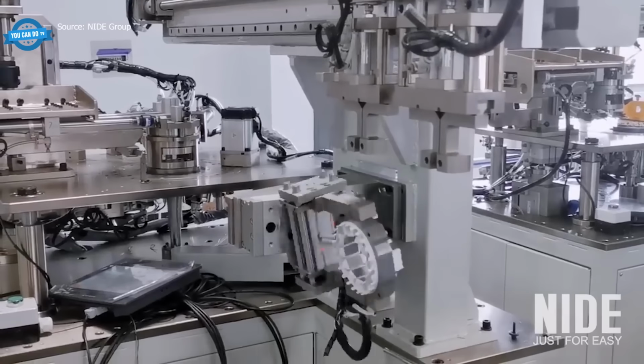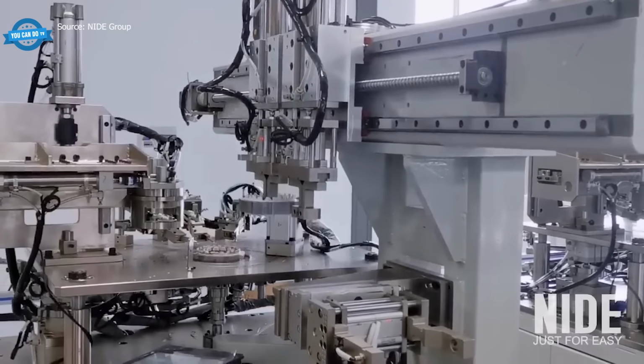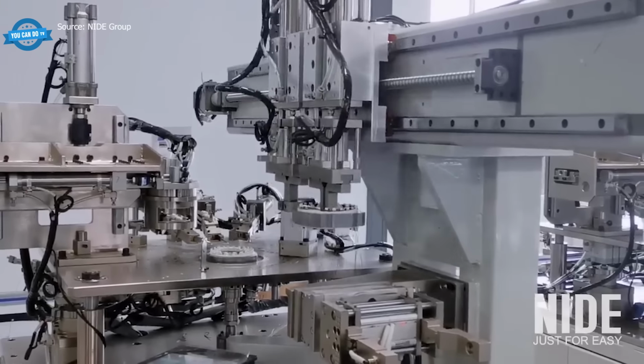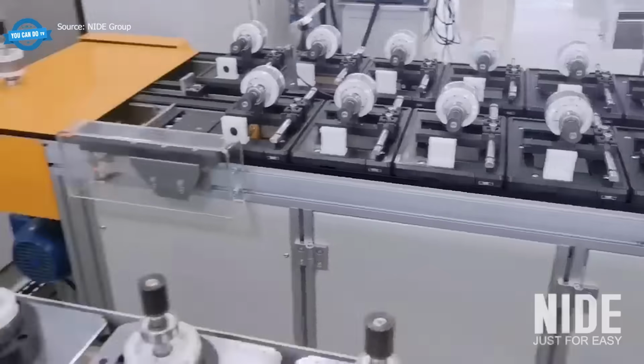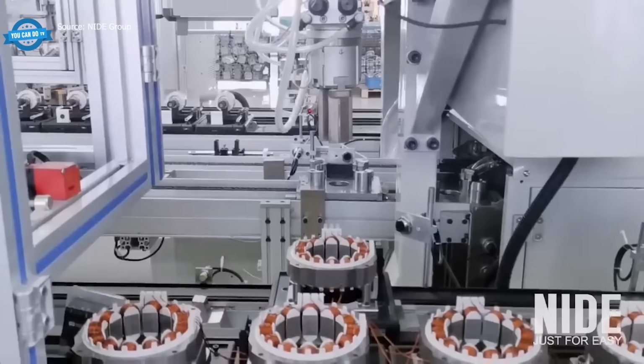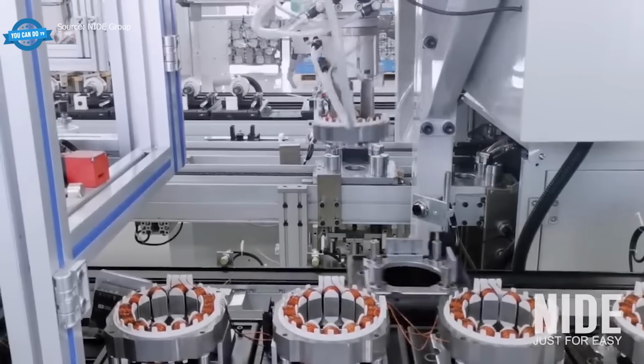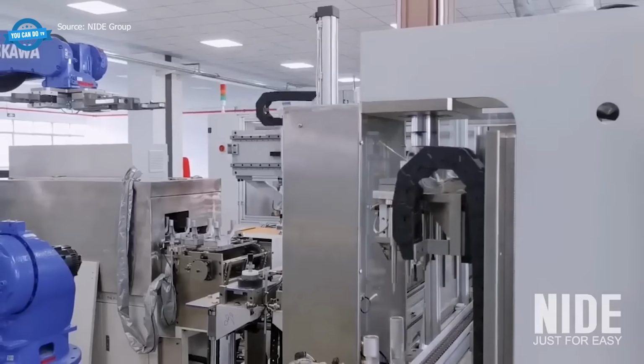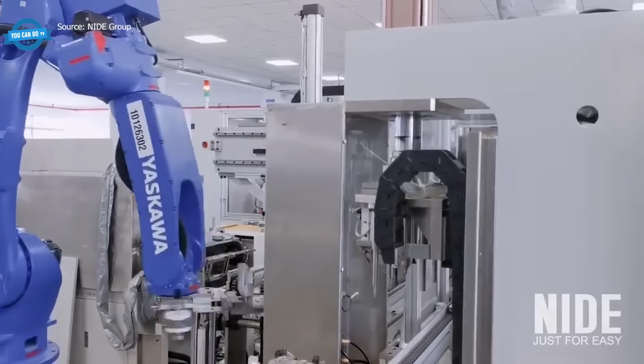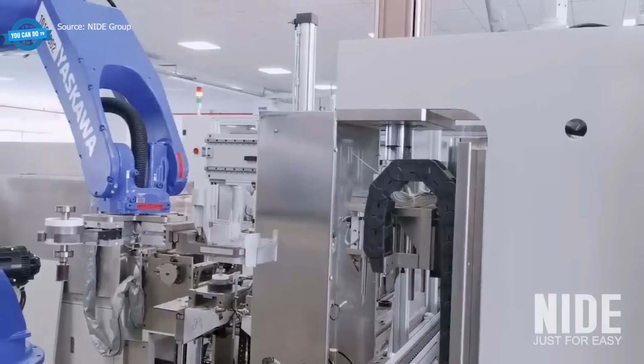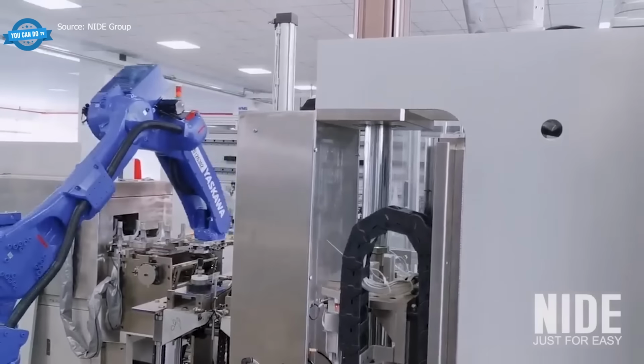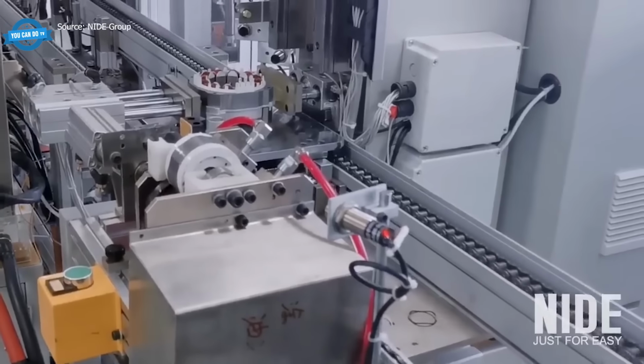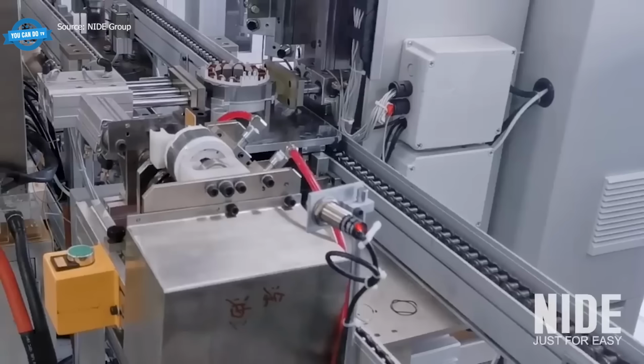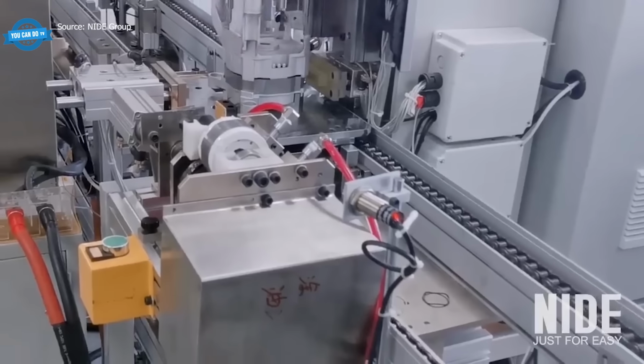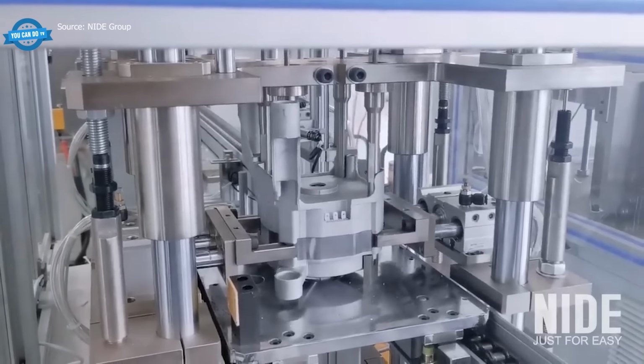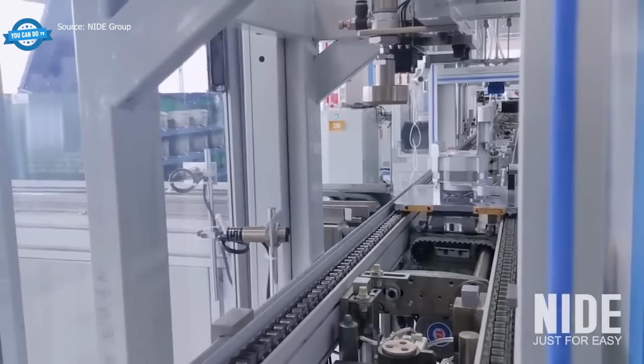Remove the commutator, remove the brushes, and the wear mechanism that limits DC motor service life in a traction application disappears with them. A fully automated BLDC assembly line winds and inserts stator coils, hydraulically presses the stator core, robots handle the housing, and a press assembly joins rotor, stator, and housing into a finished unit without manual intervention at the critical tolerance stages. Sensors verify position at each transfer point. The completed motors exit the line with power leads already connected, ready for electrical testing. The absence of brush gear means the only wear surfaces remaining are the bearings, a fundamental change in the maintenance profile of the drive system.